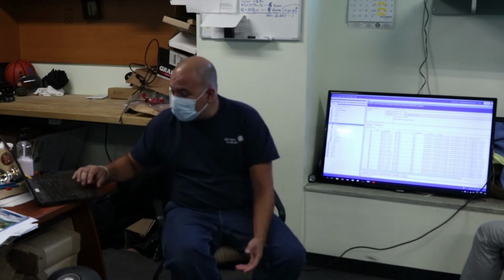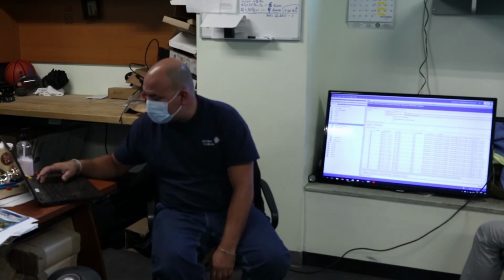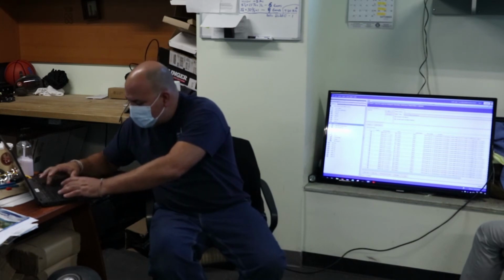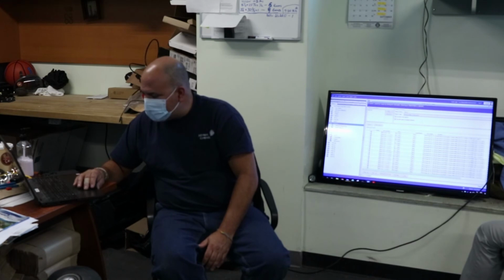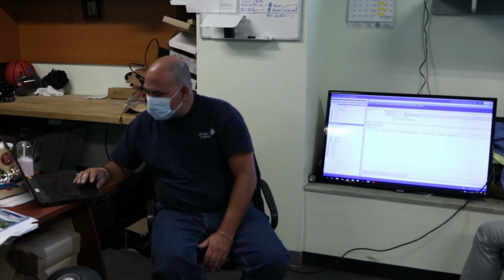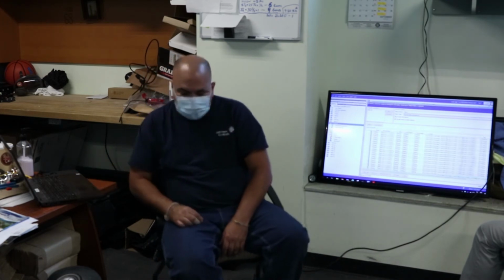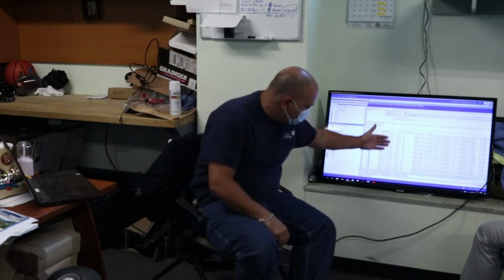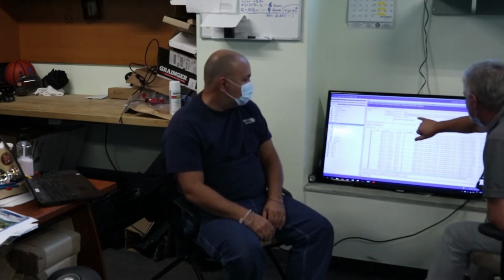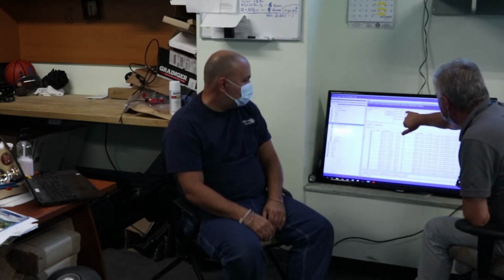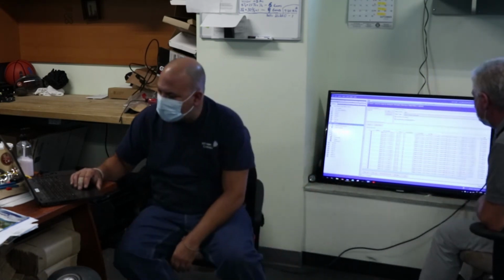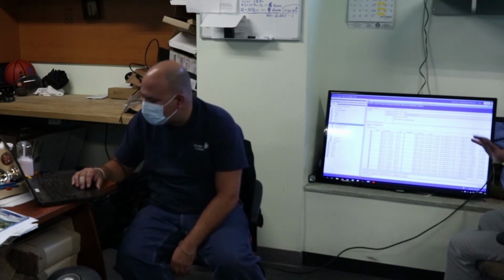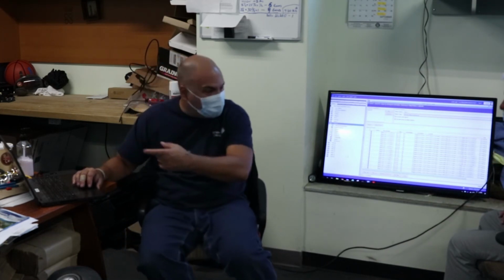Right, well, let's say I want to even see what the damper position is. Right, because the damper position is basically what's resetting your discharge air temperature. So I can see where the dampers are. In the front, you have to put the asterisk, so if I look at it, it takes all of them in that NAE.